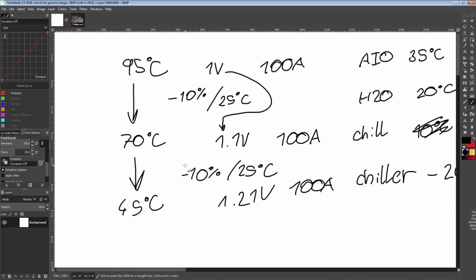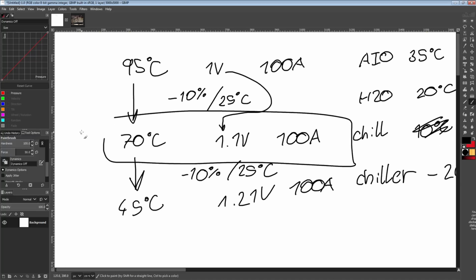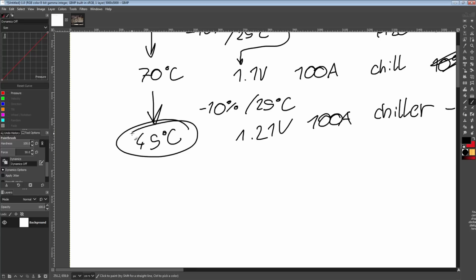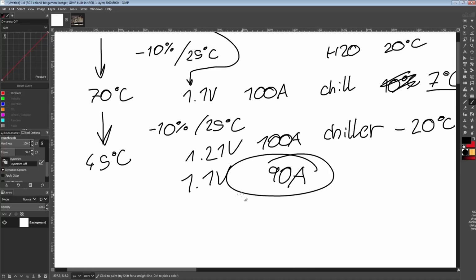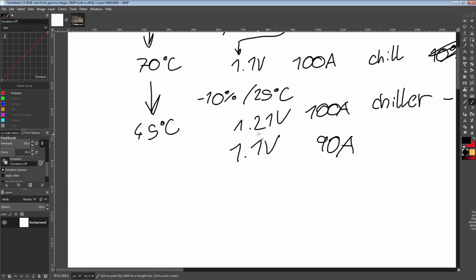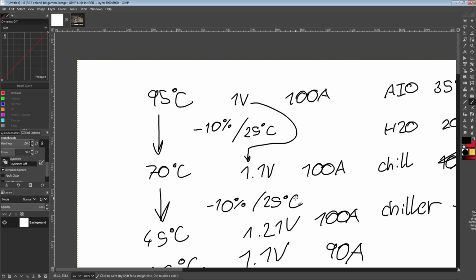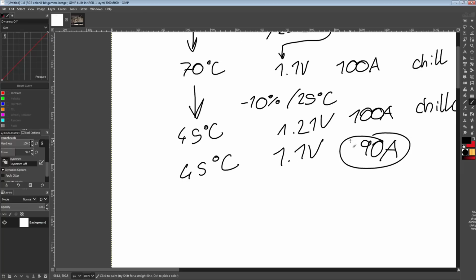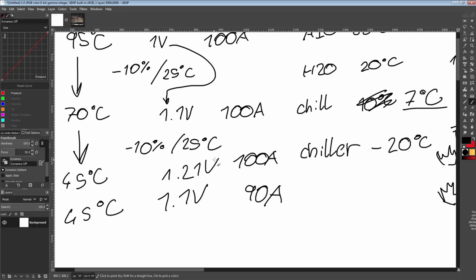Basically, this right here, I would be concerned that this probably isn't okay. But if you went down all the way to 45 and then ran 1.1 volts, you'd be getting 90 amps, and I would feel like, okay, this is probably pretty damn safe. 45 degrees, 1.1 volts, 90 amps, you're pulling less current than at 95 degrees, and you're actually probably running around the same power consumption.